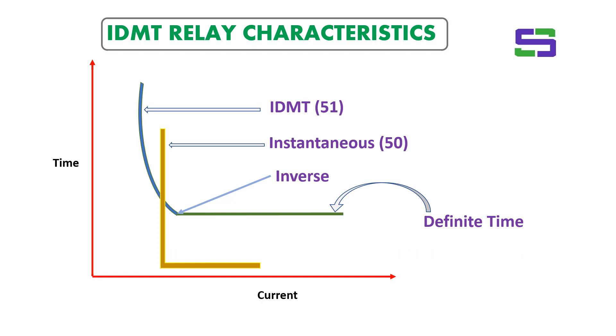The instantaneous trip is not at zero milliseconds — the relay will take some time to operate — but there should be no intentional time delay. That is why it is called instantaneous. The instantaneous element operates instantaneously when there is a very high magnitude short circuit fault current.